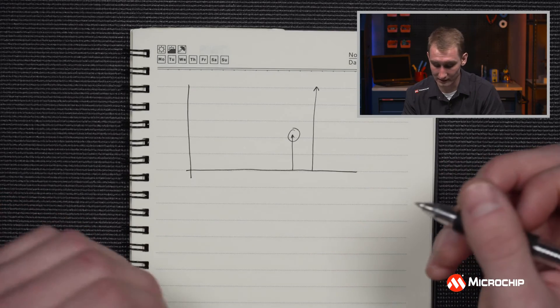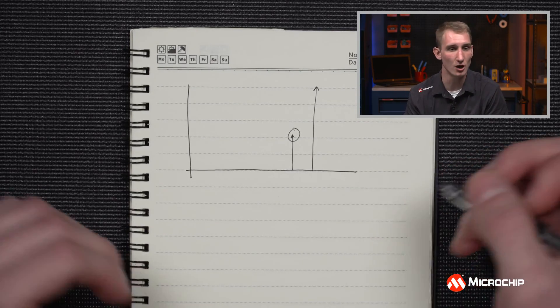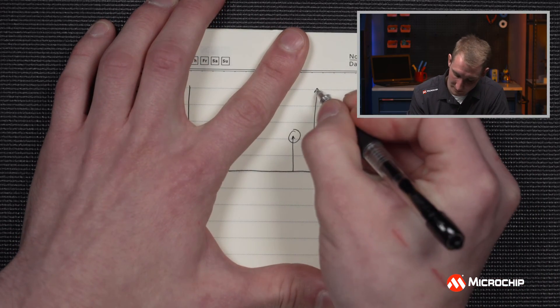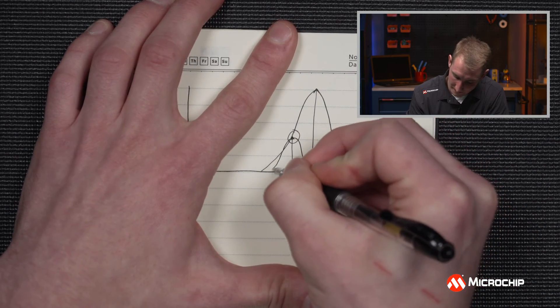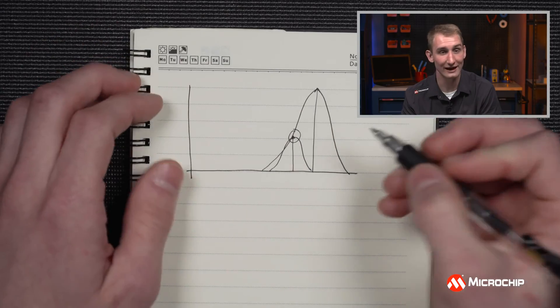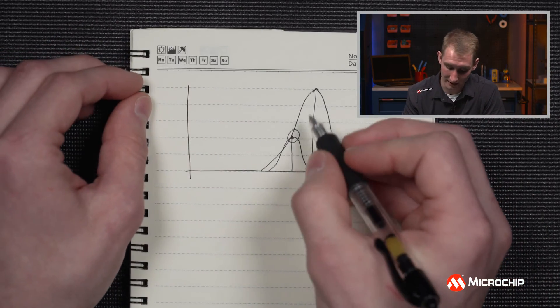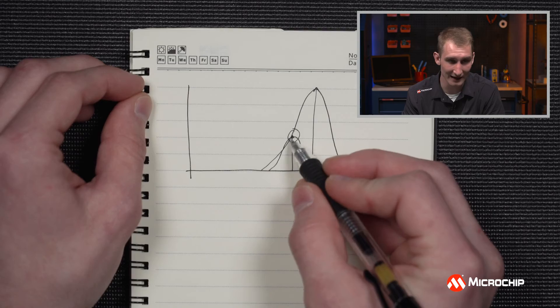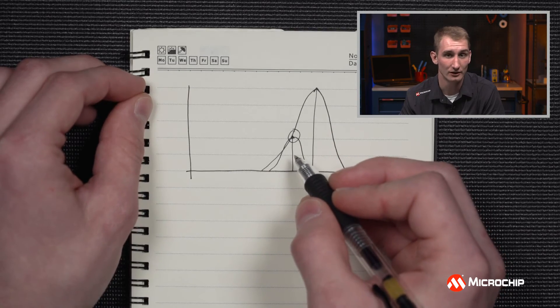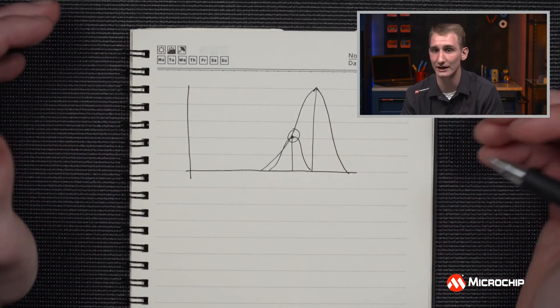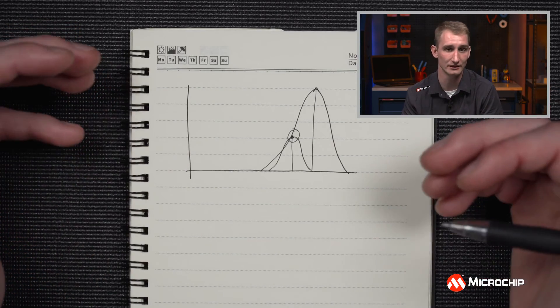So let's say we're working with a really noisy low-end oscillator and the noise that your receiver picks up goes like this. What you'll actually do is you'll see that the noise from this signal will completely mask what you're trying to measure, leading to unreliable communications or missing transmissions. So in this situation phase noise is essential and measuring using the 53100 will give you confidence that you're choosing the right oscillator for your design.